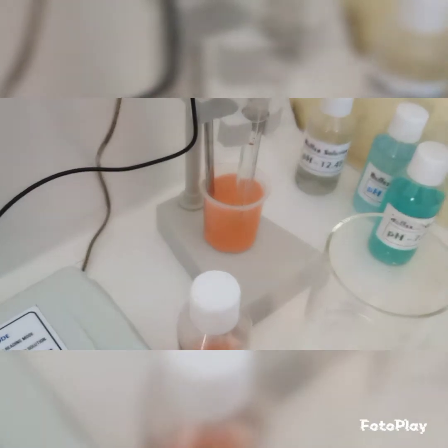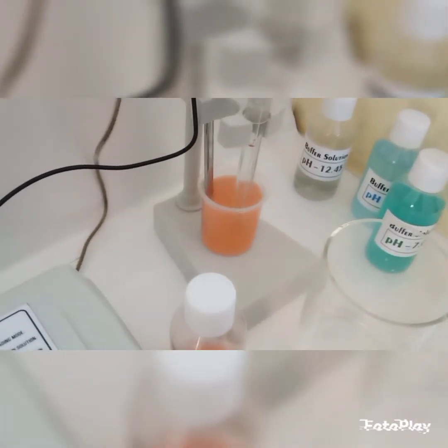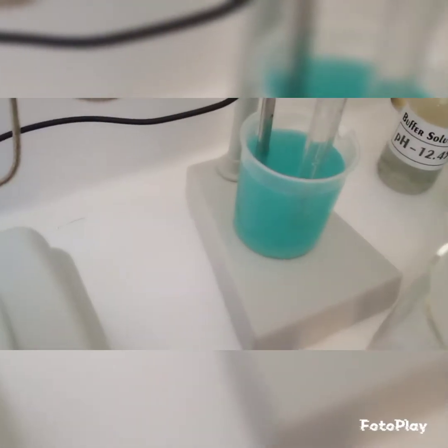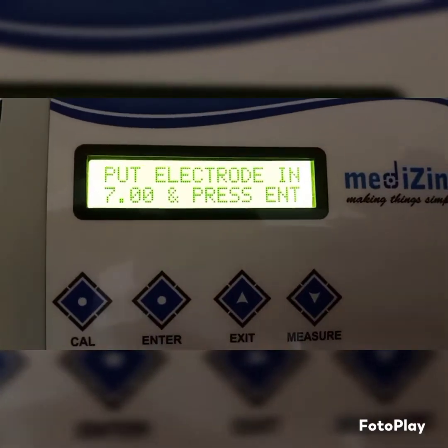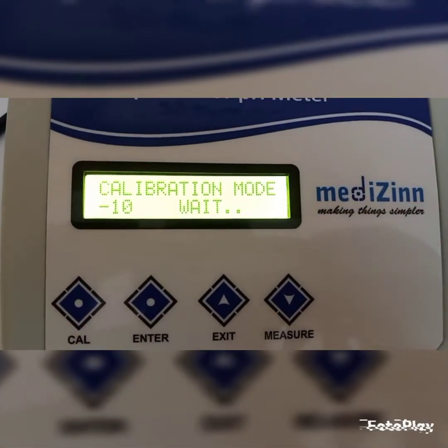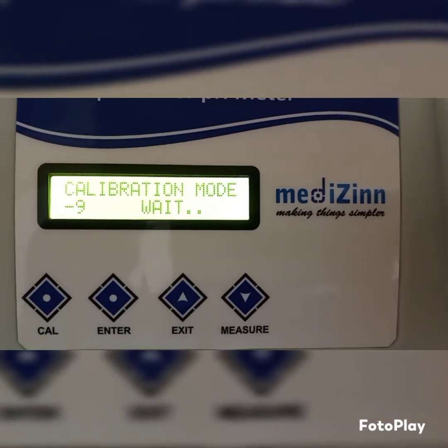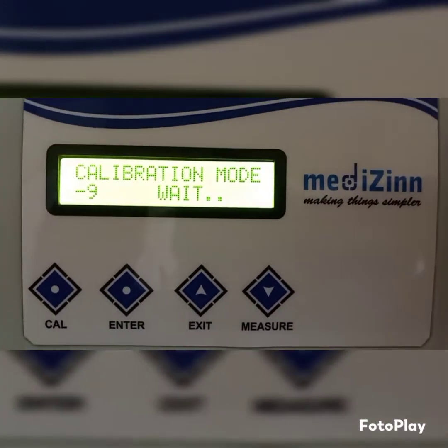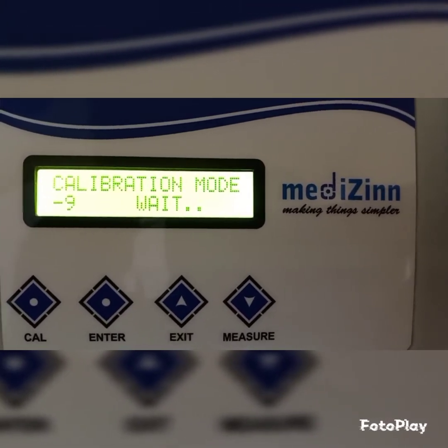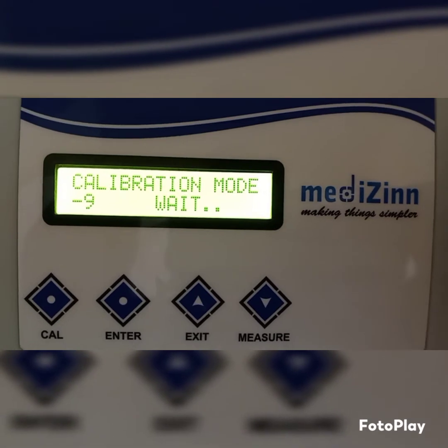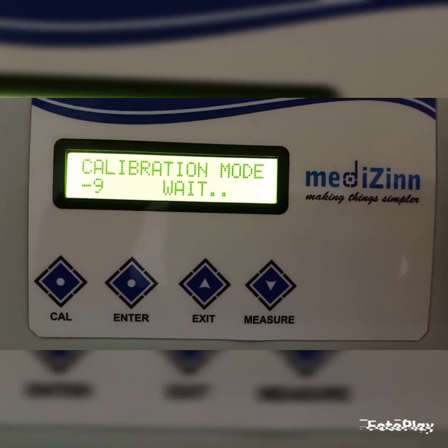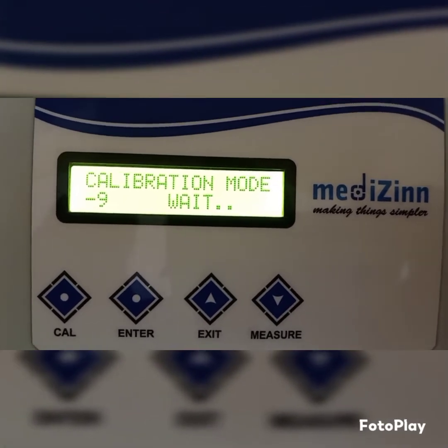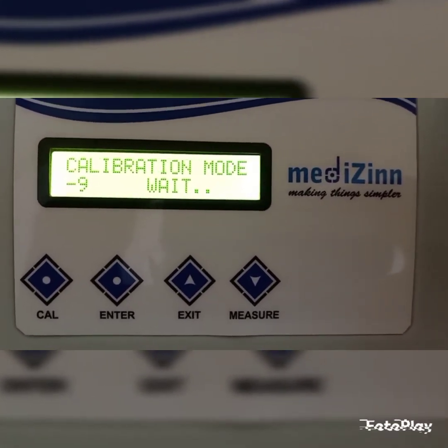Wash the electrode and temperature probe thoroughly using distilled water and put the 7 pH buffer into the beaker. After washing, put both the electrode and temperature probe into 7 pH buffer, and after that press enter key. Corresponding to 7 pH, again some analog value is there. We have to take care that it should be stable, and that value is around -30 to +30. Again we have to wait for approximate 2 minutes.